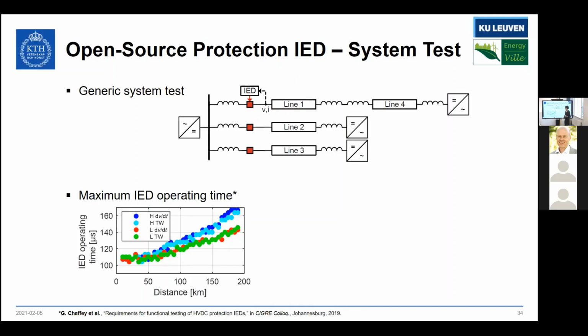And you can see how for very close faults, the detection is around 100 microseconds here, and then for faults that are a bit farther away, the IED operating time is a bit longer. That has to do with the fact that for faults that travel through the cable, the steep voltage collapse is dampened, and that's why it's a less dramatic dV/dt and it takes a bit longer to detect. And we also investigated several scenarios for high inductance, low inductance, and several algorithms, but it's basically the same trend.